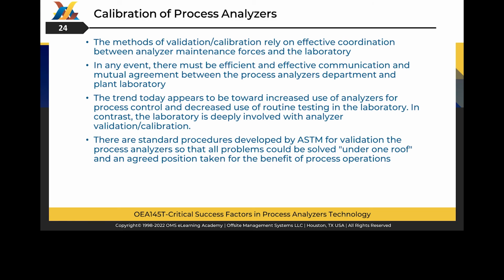When a new stream analyzer is initially installed, or after significant maintenance has been performed, a set of tests must be performed to demonstrate that the analyzer meets the manufacturer's specifications, the historical performance standards, and the specification limits set by the process being analyzed. These diagnostic tests may require that the analyzer be adjusted to provide predetermined output levels for certain certified reference materials, or CRMs, or compared with other reliable analyzers.